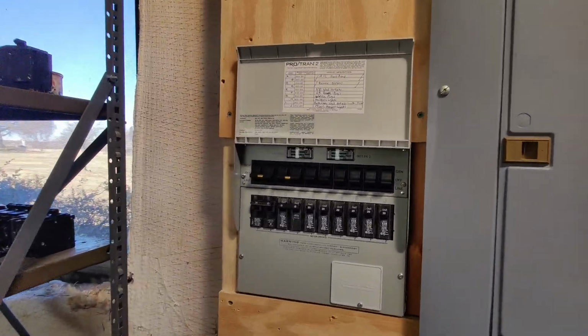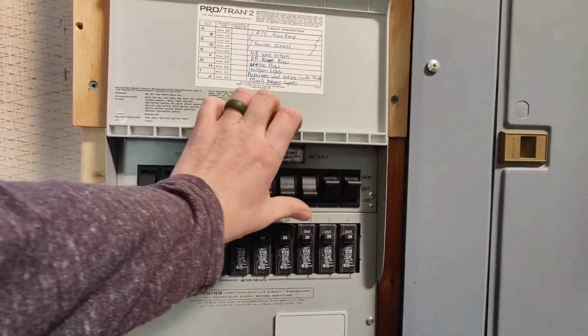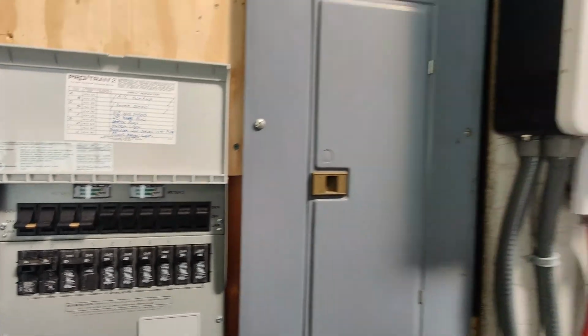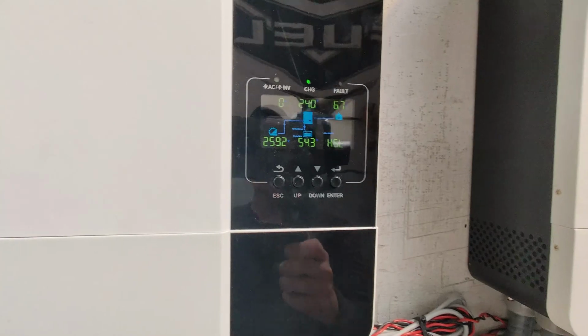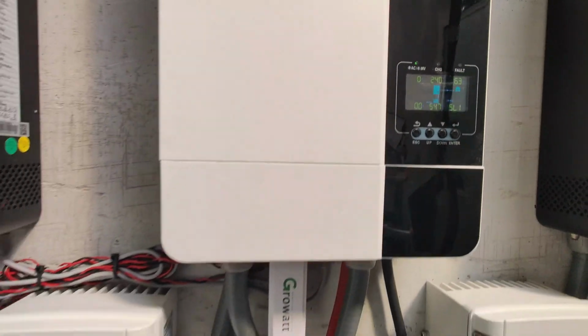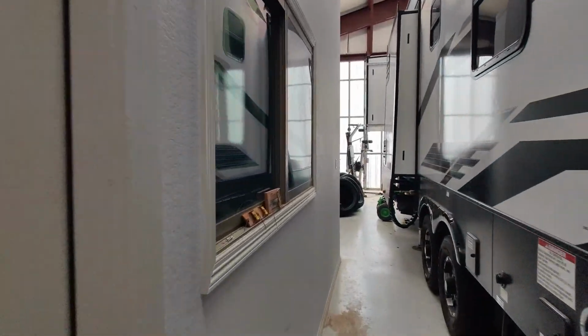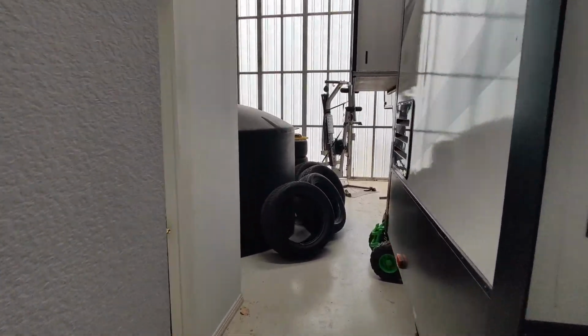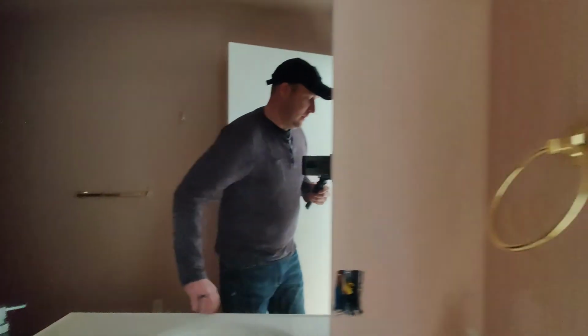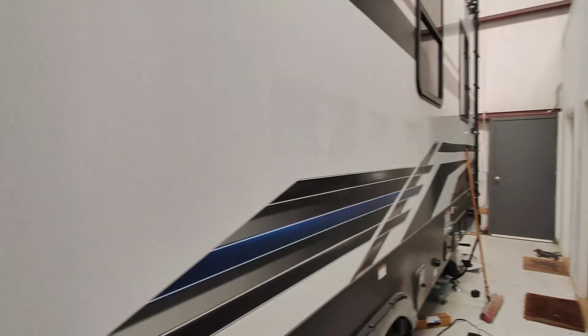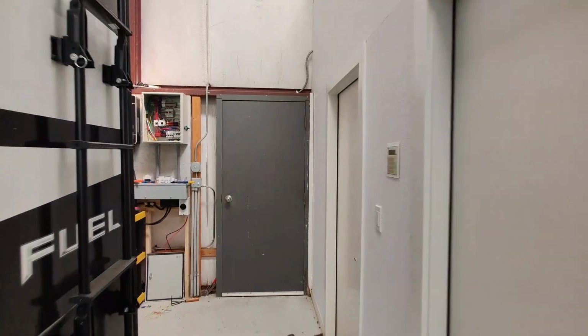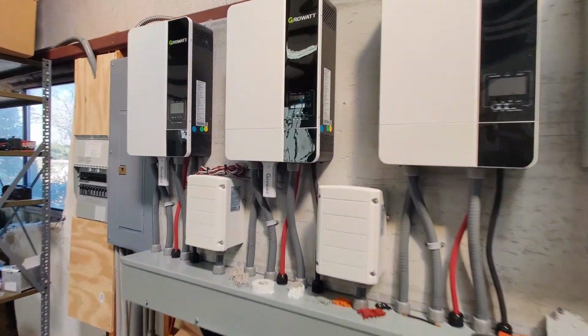and I'm good to go. I can start putting loads on this, and we're going to go ahead and throw a load or two on it. So let's come over here to our power panel. Put all these on the generator. Now I'm putting a whole bunch of loads. So we've got 6.5% on each one. So let's go turn the well pump on, or water pump. So I've got a water pump that operates the. So this is a 120 volt water pump. We'll see that this thing is going to put a load on here.